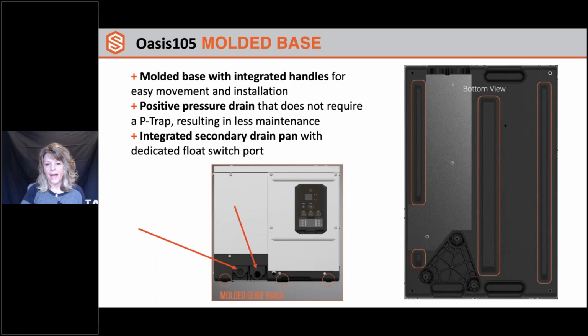I know in the past with crawl spaces, we've had requests for being able to wire a float switch to the dehumidifier. That is one of the reasons that we really drove home on this unit, listening to our customers, that it's not just ducted units where we want that float switch. It's also in a basement space or in a crawl space where we want that dehumidifier to shut off if there is water detected.